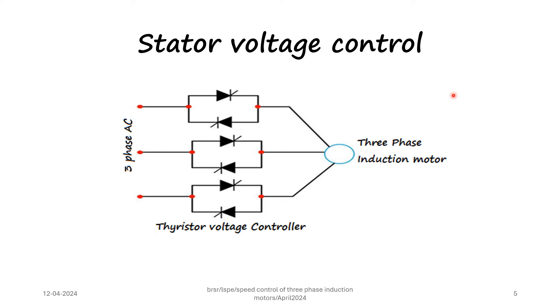Stator voltage control is a method by which the speed of a three phase induction motor can be changed. In this method the supply available to the stator is changed using a thyristor voltage controller, which consists of three pairs of thyristors. Two thyristors are connected back to back and each pair is connected to a phase. The supply voltage is changed by changing the firing angle of the thyristors. The torque developed is proportional to the square of the supply voltage, and hence the motor speed changes — but there is no change in the synchronous speed.